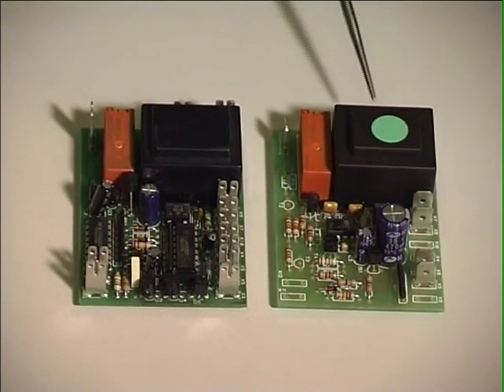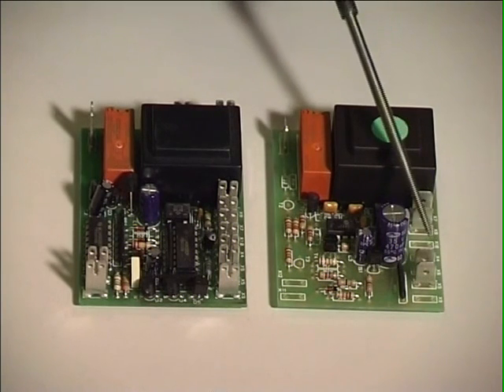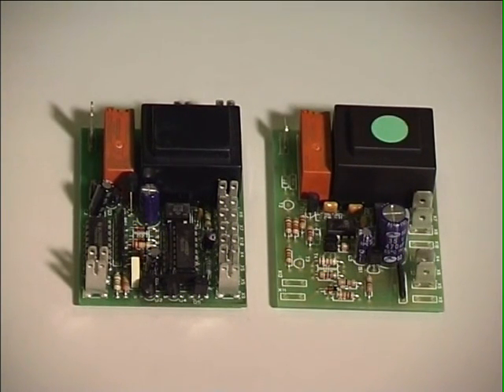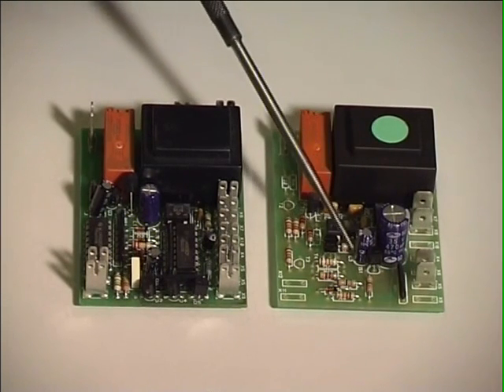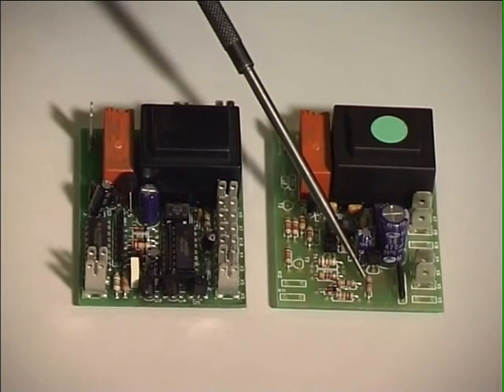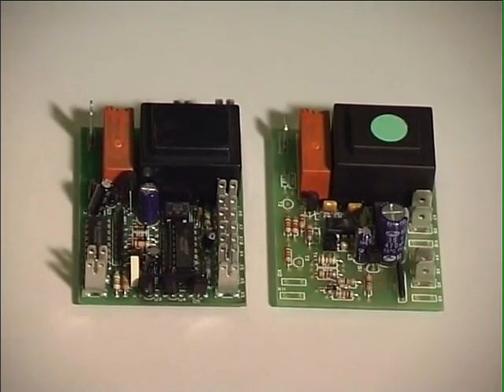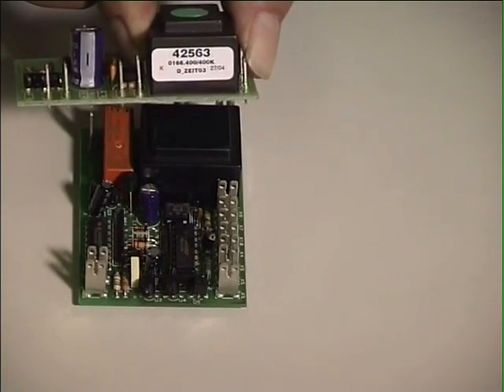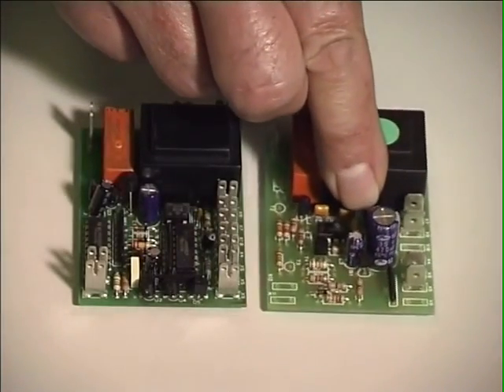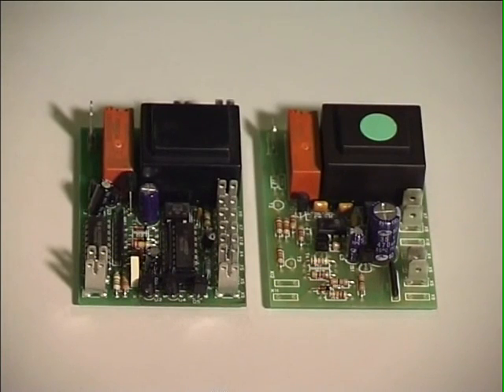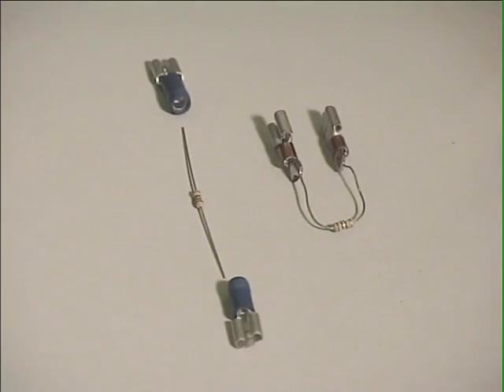In the new version, you will find here the contacts for current supply. The connectors for the red pressure switch by 5 and by 6. And the connection for the safety coil control. You can turn off the 20-minute safety cutout by removing this resistance. The article numbers for these circuit boards are 42563 for 400 volts and 42564 for 230 volts. This is a set for making an electronic bridge consisting of 2 plugs and a 100 ohm resistance.